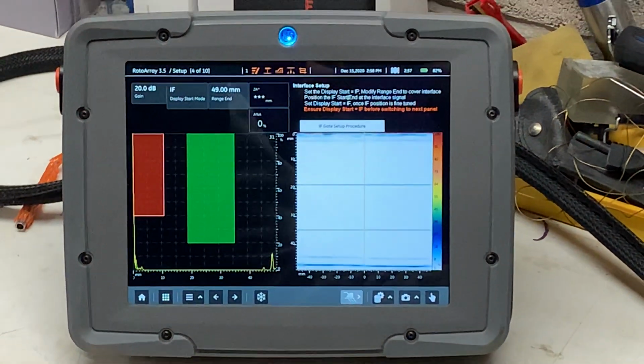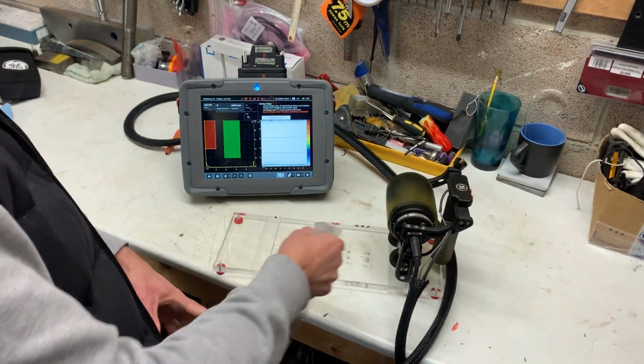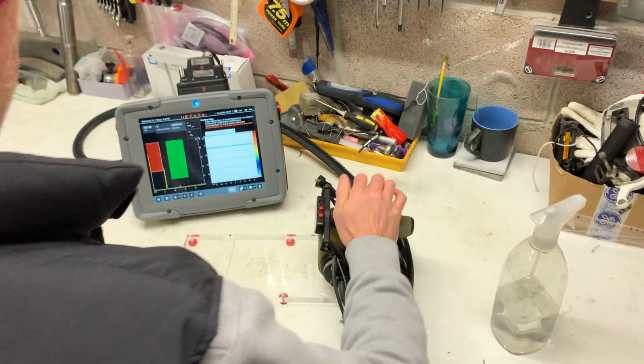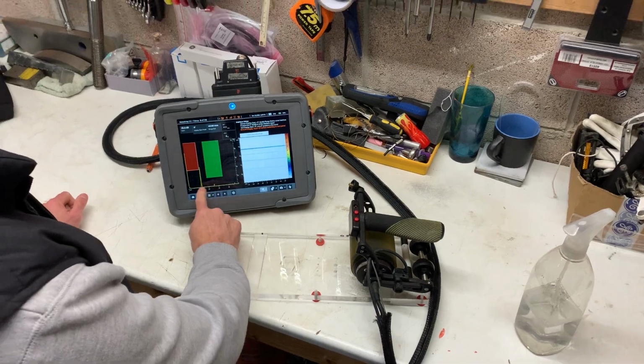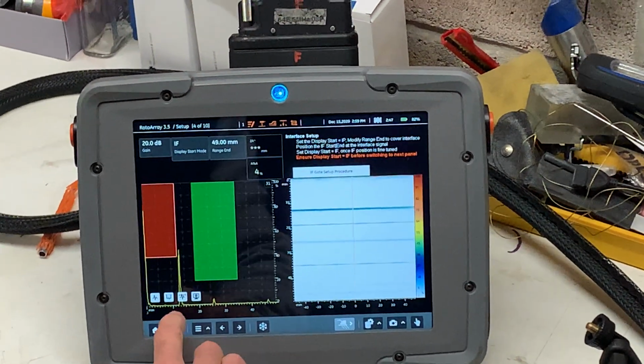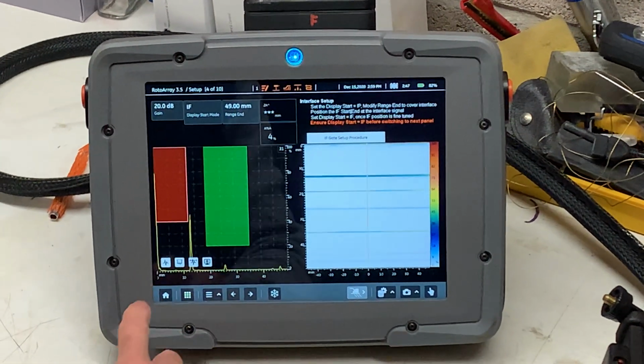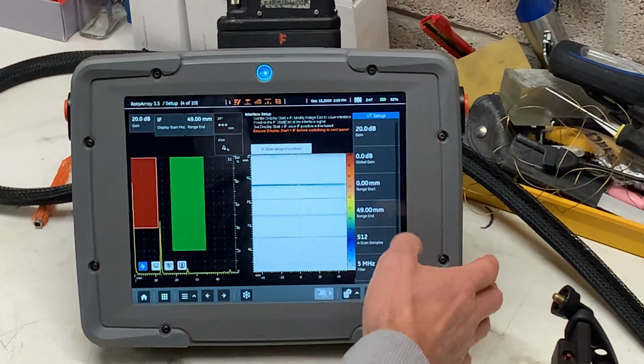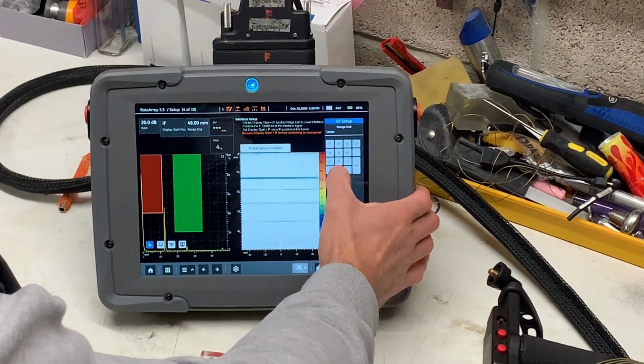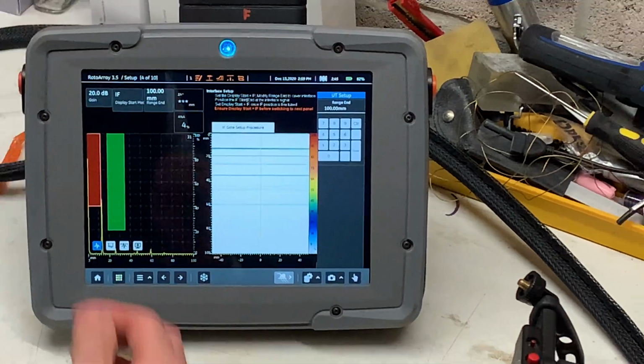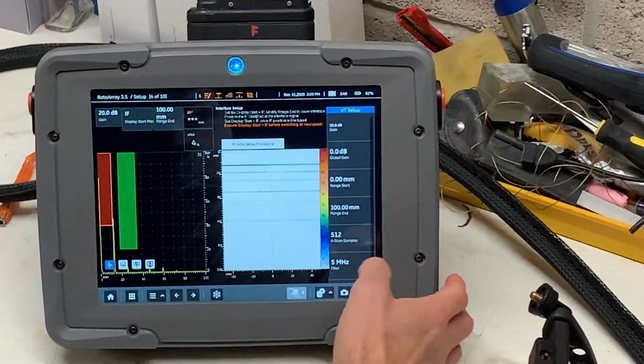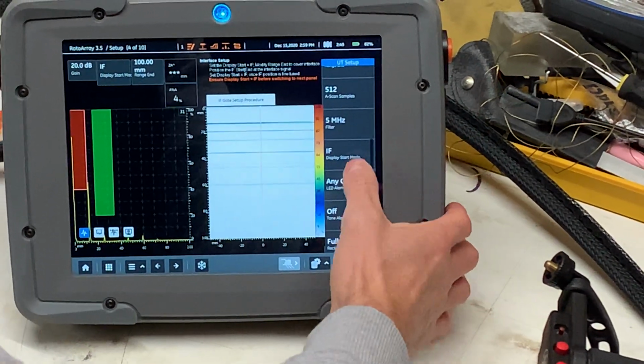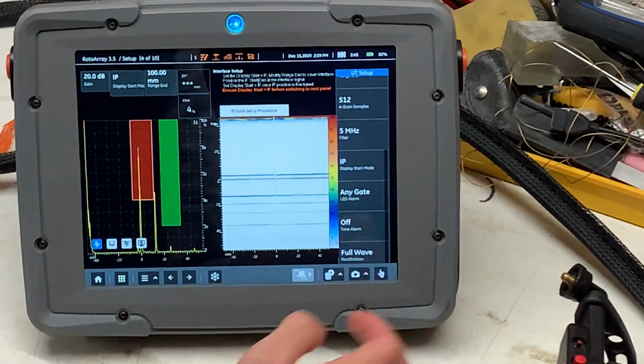So what we need to do first then is just put a little bit of water on the part, sit the rotor down on the full back wall thickness, tap the screen here and go into our ultrasonic settings and set some stuff up. So let's put a big range on here so we can see everything. So 100 mil, like that. And let's tell it to start from the initial pulse, the IP here.